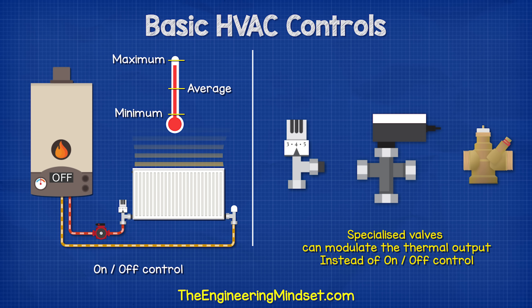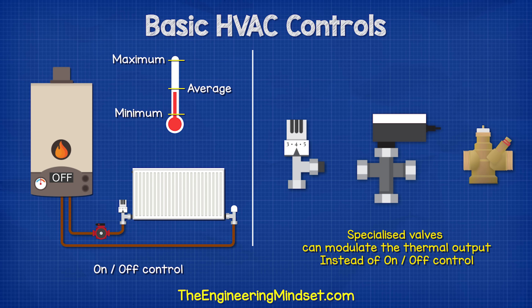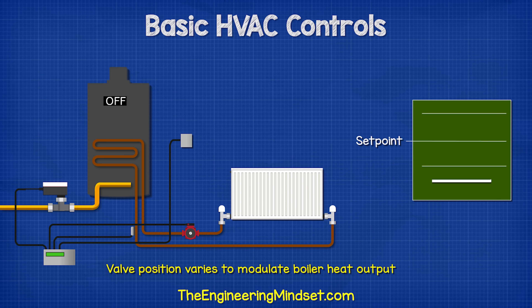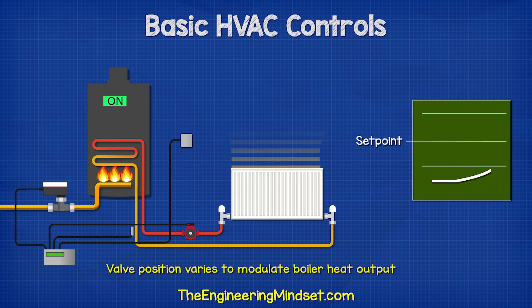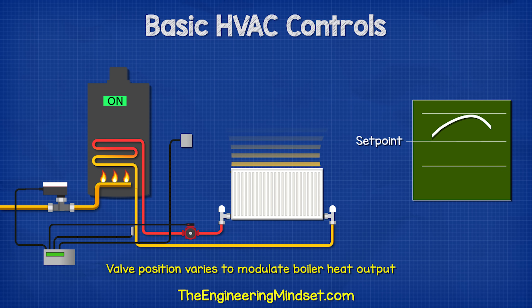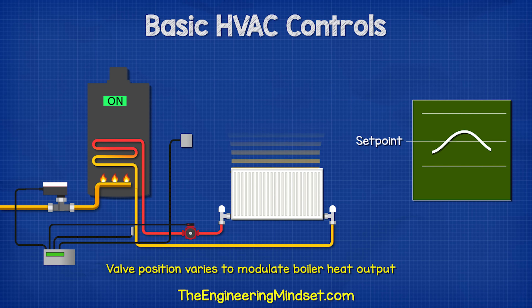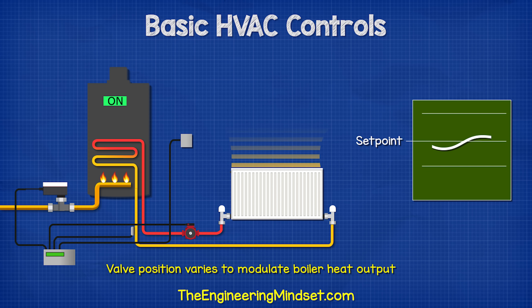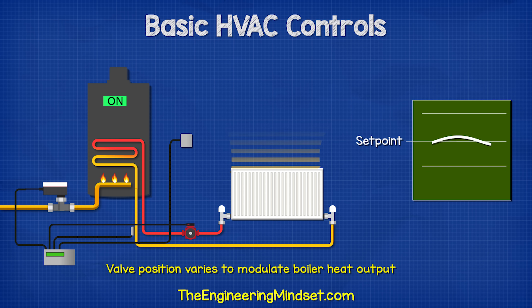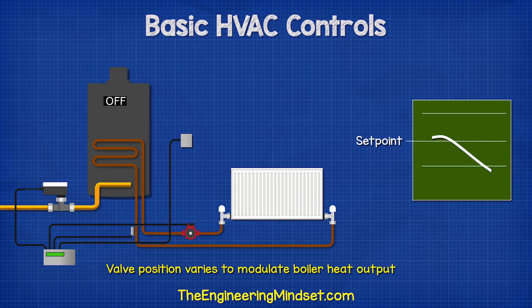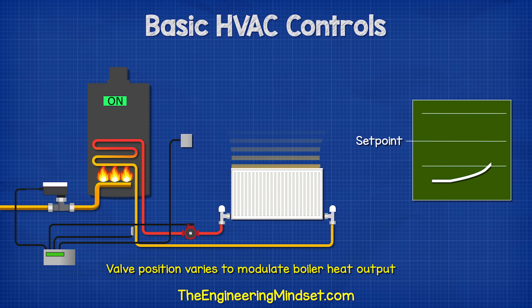On-off control makes it difficult to maintain a desired temperature. Instead, we can use special valves to modulate the thermal output, keeping the temperature within a certain deadband. In a simple heating system, when the gas boiler turns on, it will run at full power to heat the water, but then it reduces the gas supply by using a motorized valve. This reduces the heat output of the boiler instead of turning it off.